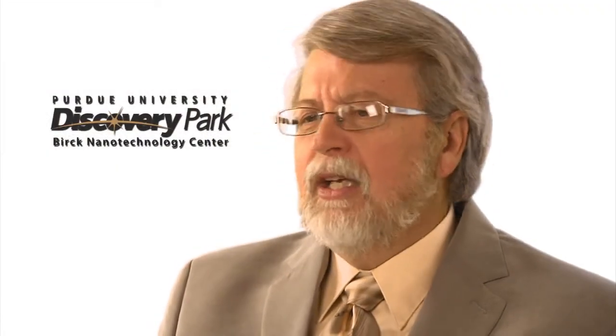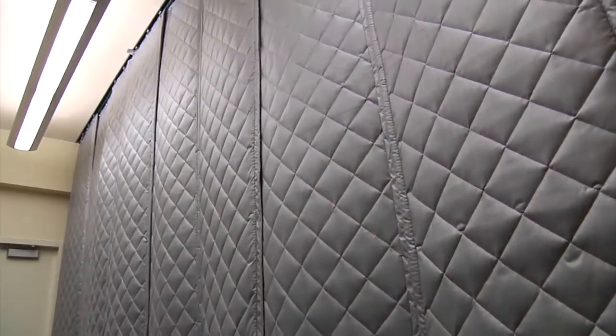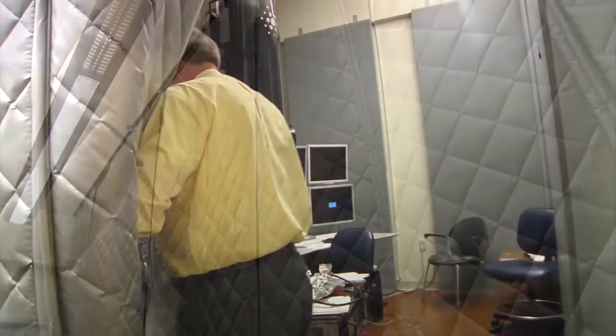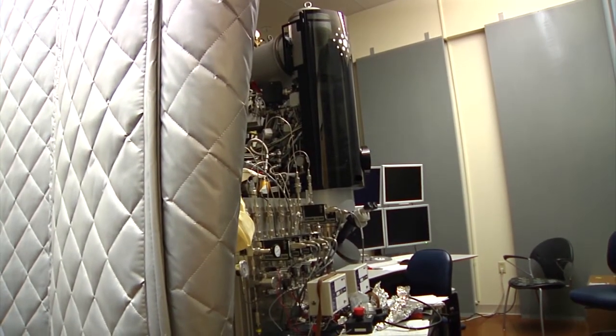Temperature and EMI, not as much, but the acoustic was something that was very important in there. So we used a cork floor. We have curtains hanging around that are sound absorbing curtains. And that keeps it very, very quiet in that room. We channeled the airflow so there's no temperature differential across the column of the microscope. Very, very nicely tailored for that particular instrument.